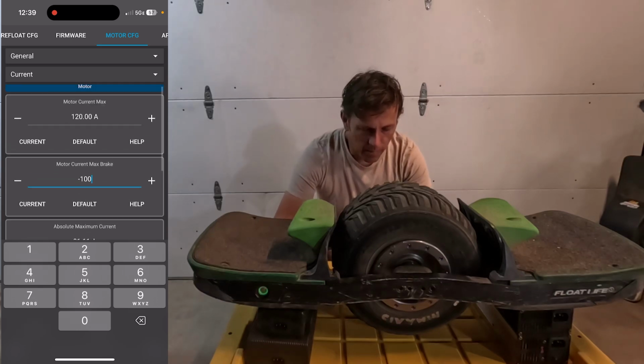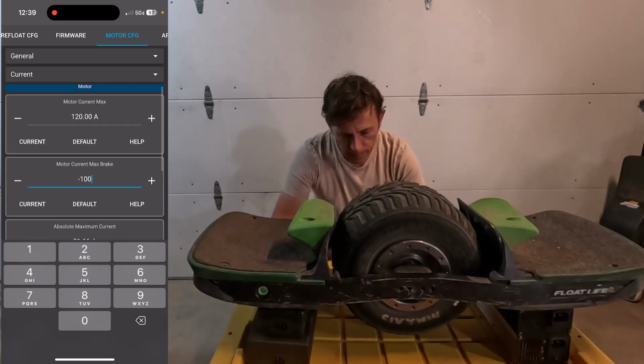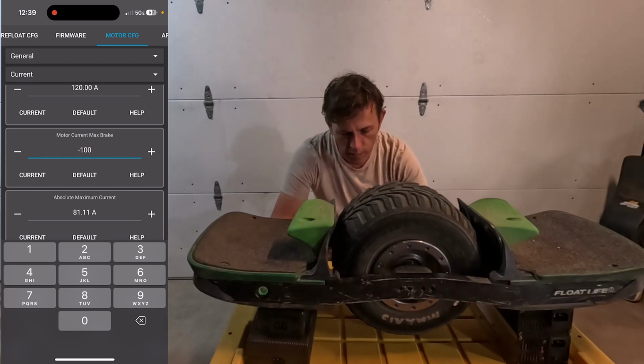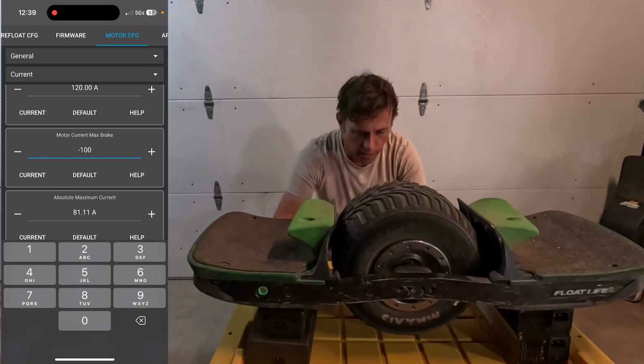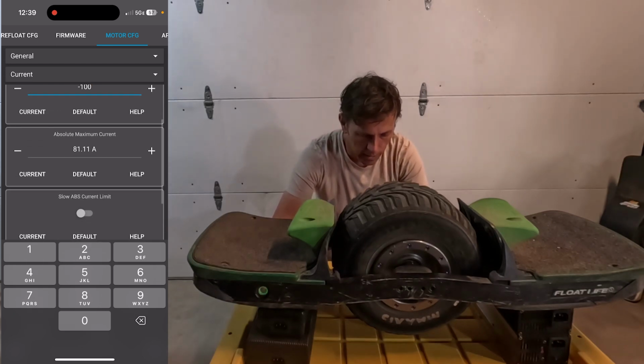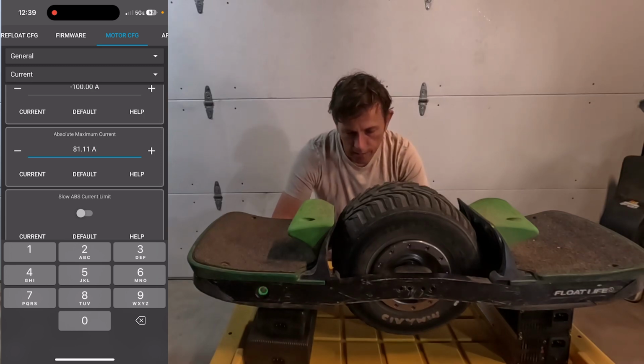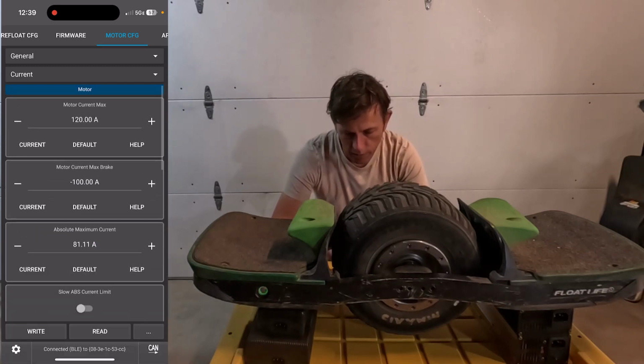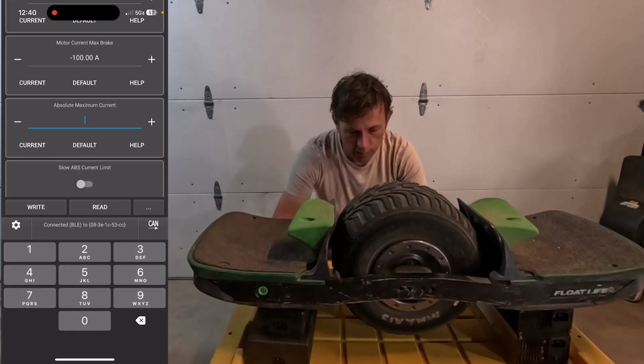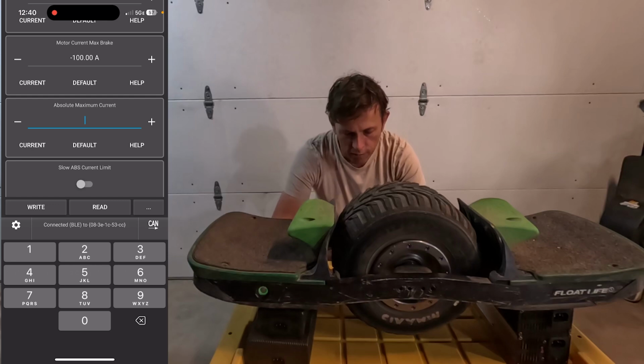So 120 is the maximum current that you want to allow, and the other one is the max braking current. You typically don't need quite as much for braking, so minus 100 for braking is plenty. Now the absolute maximum current - that depends on what you've set in max motor current. The best practice is to do 50% more than your max current, so for 120, that means 180.